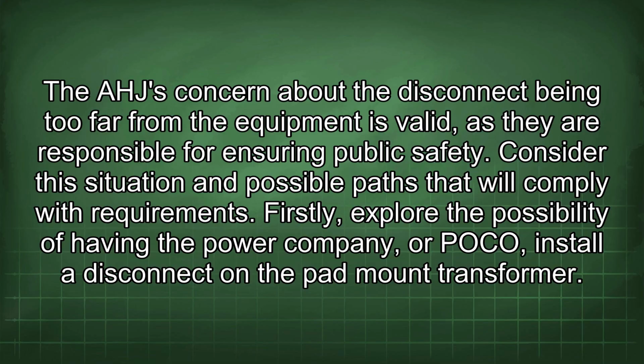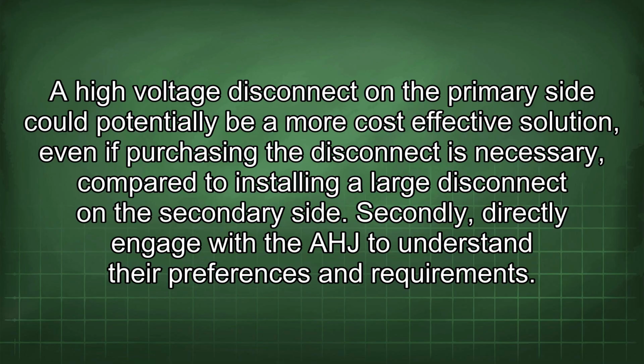Firstly, explore the possibility of having the power company, or POCO, install a disconnect in the pad mount transformer. A high voltage disconnect on the primary side could potentially be a more cost-effective solution, even if purchasing the disconnect is necessary, compared to installing a large disconnect on the secondary side.